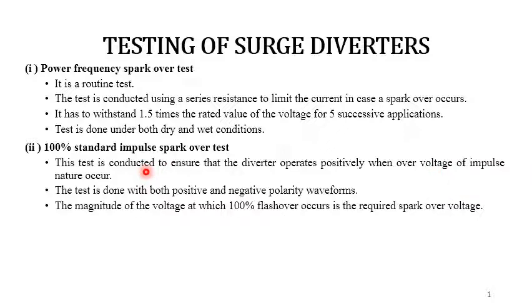The impulse generator is adjusted to give a standard impulse voltage of the preset magnitude which is specified in the specification. The arrester has to spark over every time in each of the 10 successive applications. The test is done with both positive and negative polarity of the waveforms. Sometimes the test is done by starting at a voltage level that does not give any flashover at all and repeating it in increasing steps of voltage till 100% flashover occurs at the required spark over voltage.